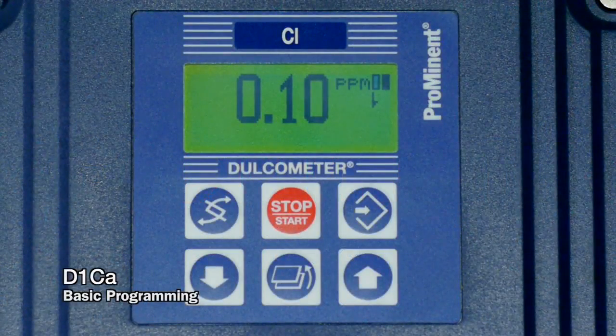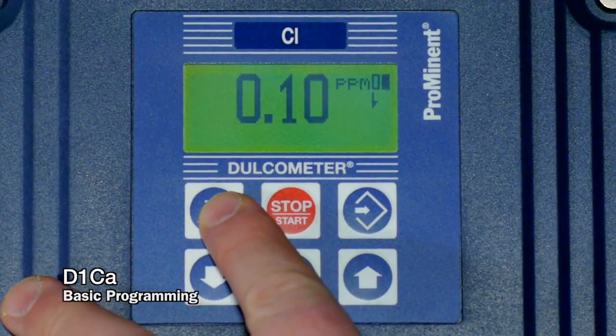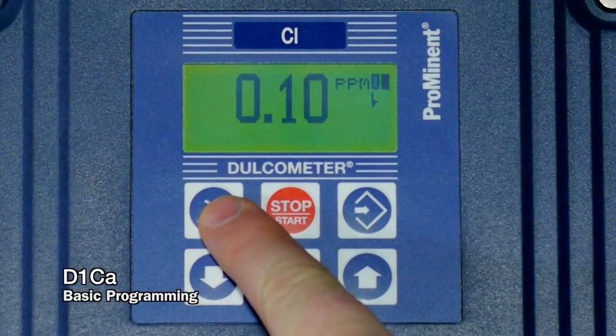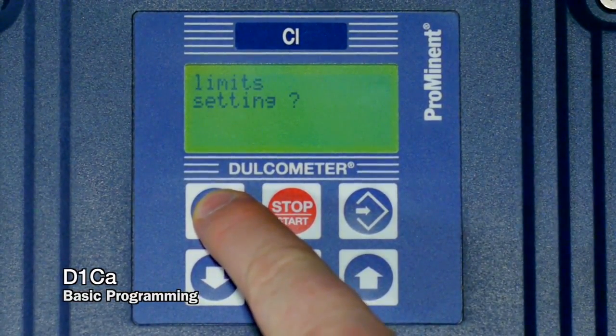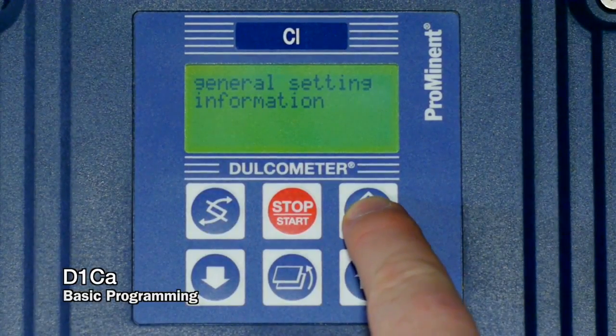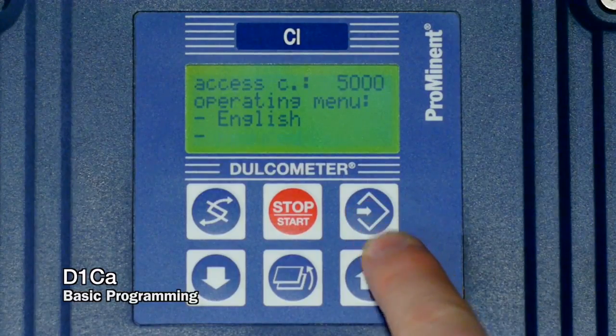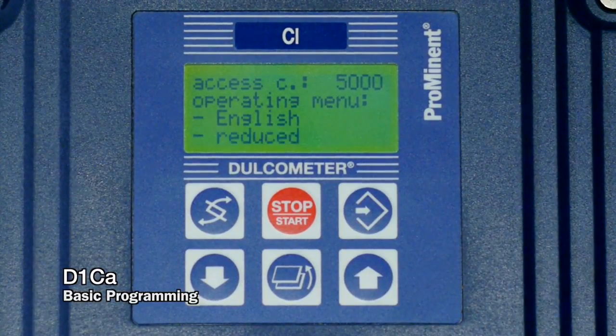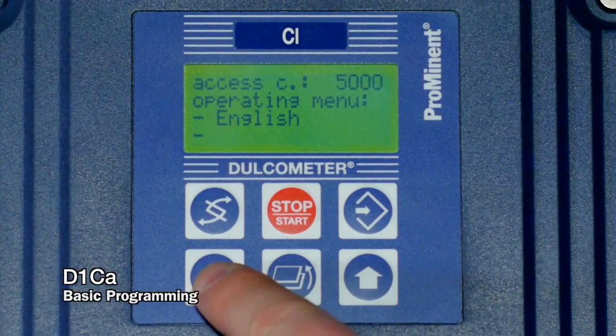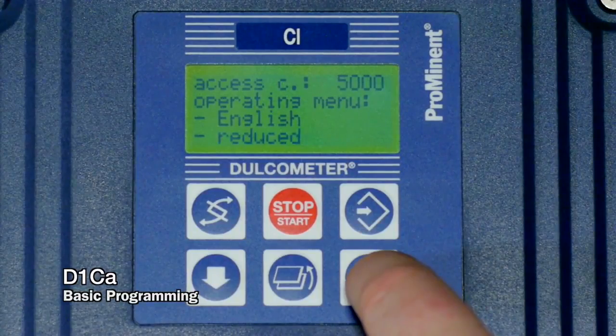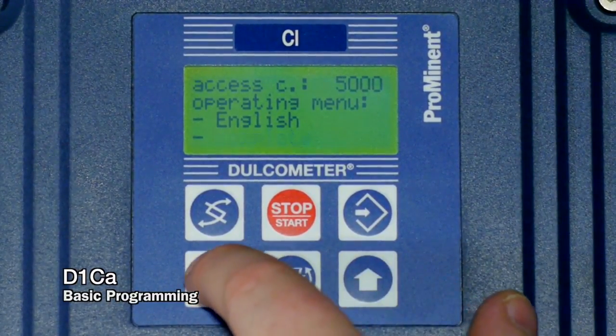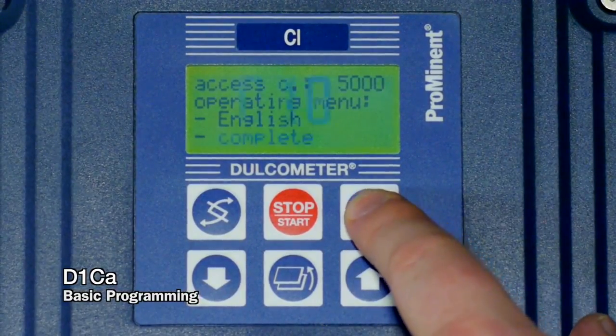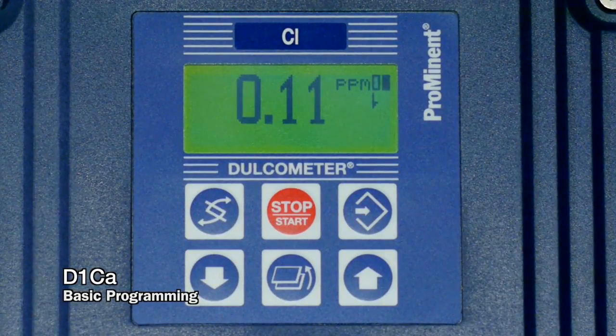This section of the video will go over some of the programming of the D1C controller. Here we're programming first to match the sensor range to the sensor that we will be using in our process. So to get to the screen to change that so that it matches, we want to hit the change key, which is the top left-hand button, until we see general settings information. Now we hit the enter key to scroll into that menu until you see the word either reduced or complete flashing. Once that flashes, we can change with either the up or down button. Anything that's flashing changes with one of those two buttons. So we get to complete, we press the enter button to accept it. See that it goes back to your main display.